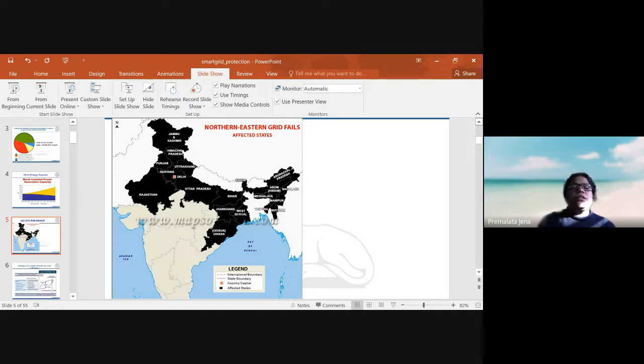Those distance relays, I hope many of you understand, maybe power systems people understand. It is actually a device, a relay or protective device. So this distance relay mal-operated, because there was no fault, no other fault scenario, but due to overloading of the line, it has been tripped.